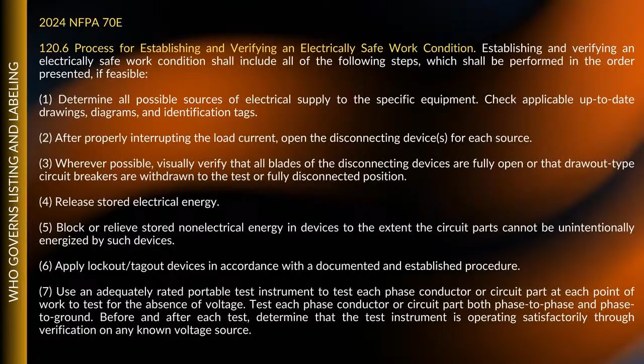Sure. I've also seen where they have pneumatic and all types of different control energies. When you do that, they have processes in place where you look at the magnitude of each one. When you get ready to do lockout and tagout, you determine which one presents the most magnitude, and that's the one that gets locked out first, then the second, third, fourth, however many different sources you have. Then when you remove the lock and tag, you do it in the opposite direction, from least to the most magnitude.